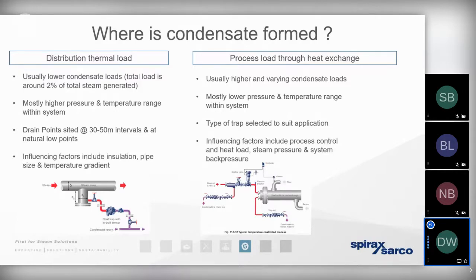So if we've got a steam network that is switched off periodically throughout the week, maybe during the weekend hours or during the evening, then for the first hour or maybe even 2 hours when the steam boiler's switched on, the steam is going to be slightly wet and it's going to be giving up more and more of its heat energy to heat the infrastructure, to heat the network. In other words, there's going to be a far, far greater condensate load at that point.